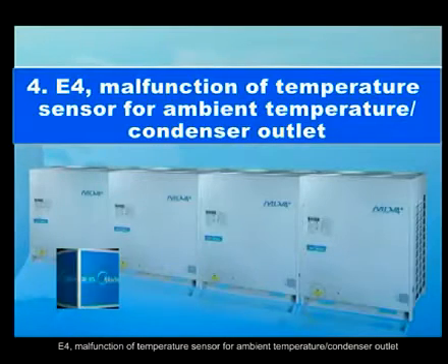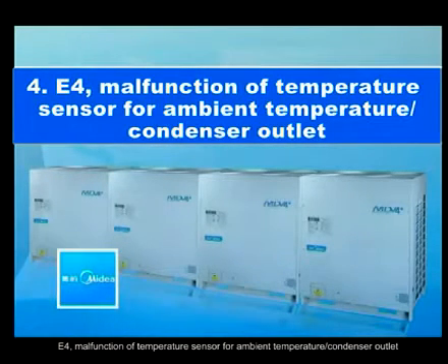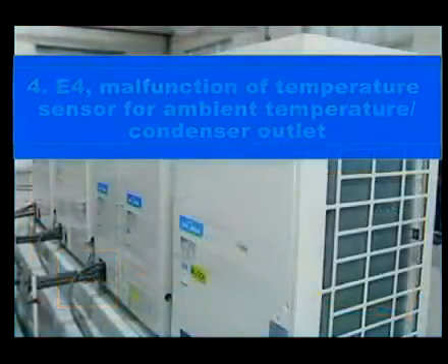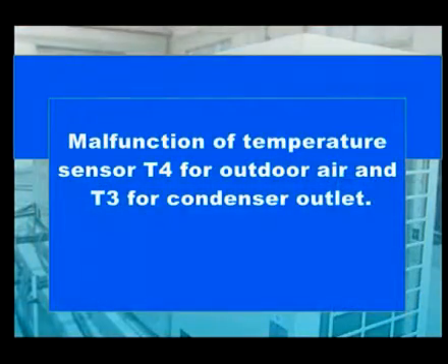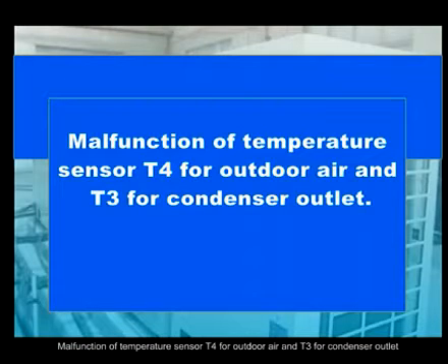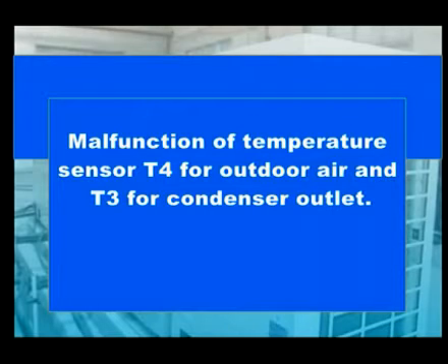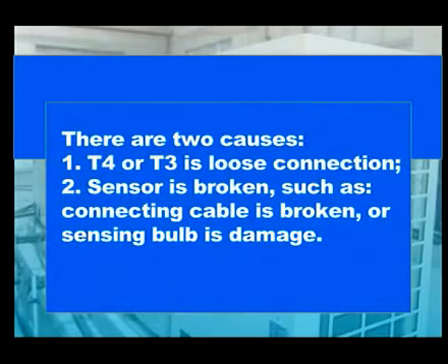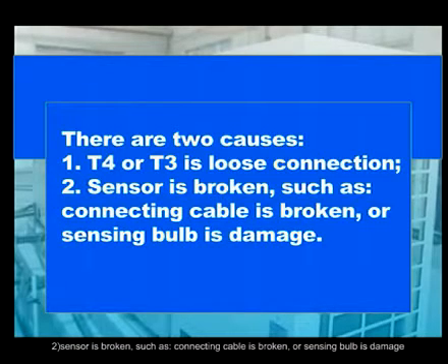E4. Malfunction of temperature sensor for ambient temperature/condenser outlet. Malfunction of temperature sensor T4 for outdoor air and T3 for condenser outlet. There are two causes. 1. T4 or T3 is a loose connection. 2. Sensor is broken, such as the connecting cable is broken or the sensing bulb is damaged.